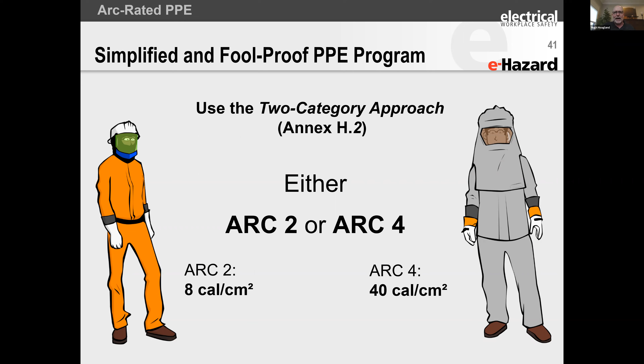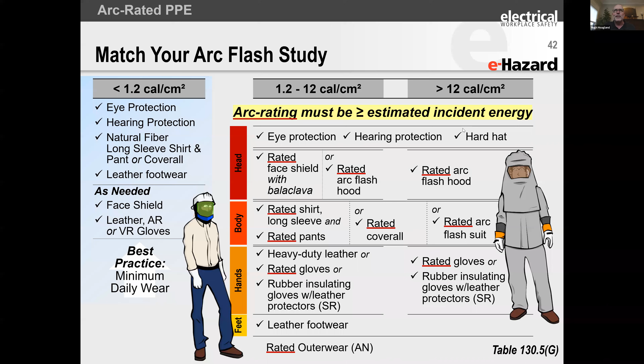That's a good way to get up to quite a few calories, and then put on the flash suits for the higher levels. We typically recommend that if companies allow t-shirts or undergarments like briefs underneath the garments, they should be 100% cotton, or at least as much cotton as possible. But from an upper torso perspective, it's always better to wear an arc-rated type t-shirt.